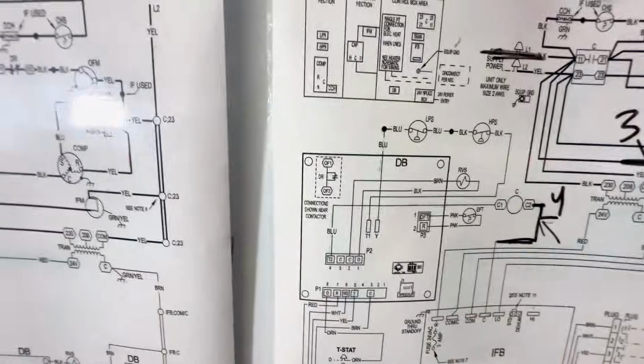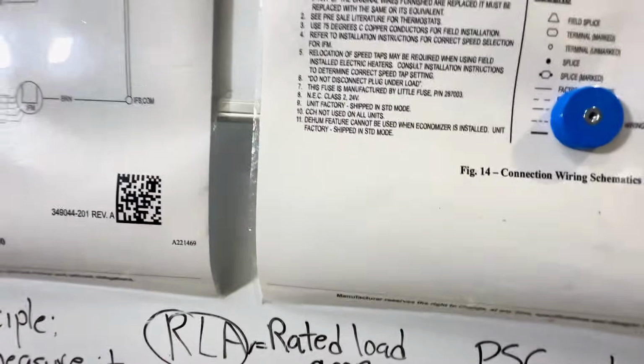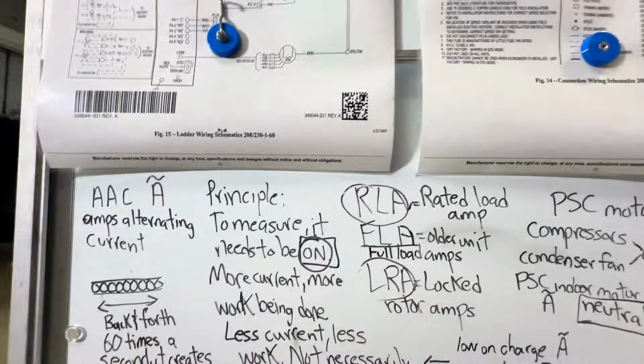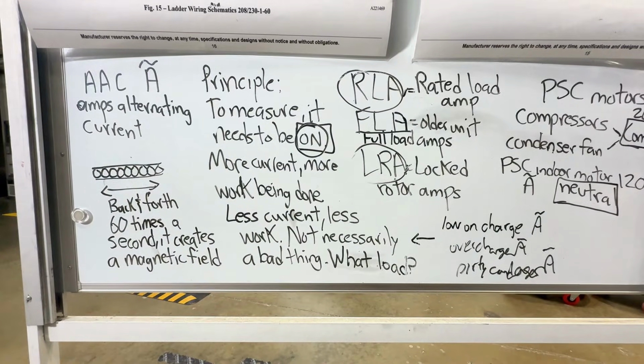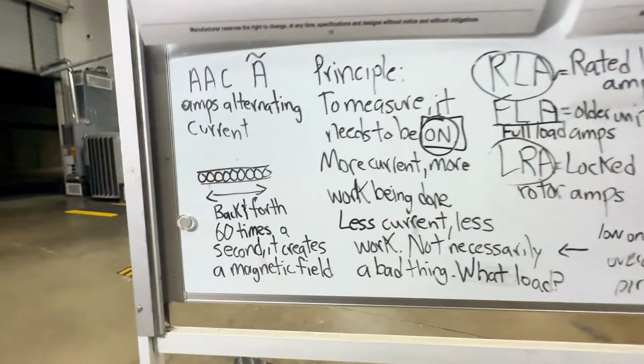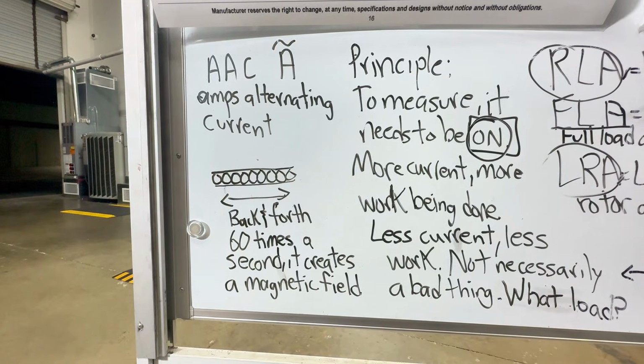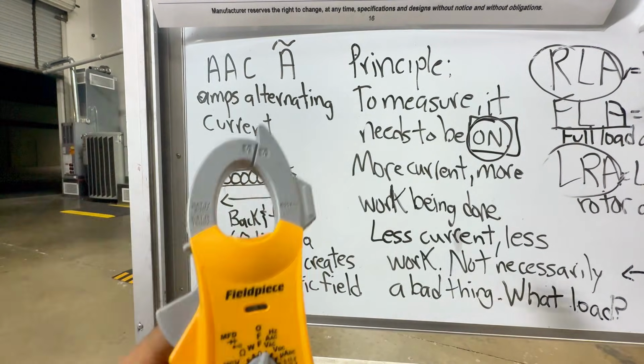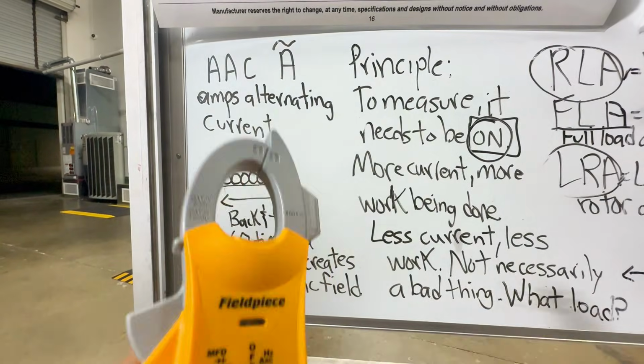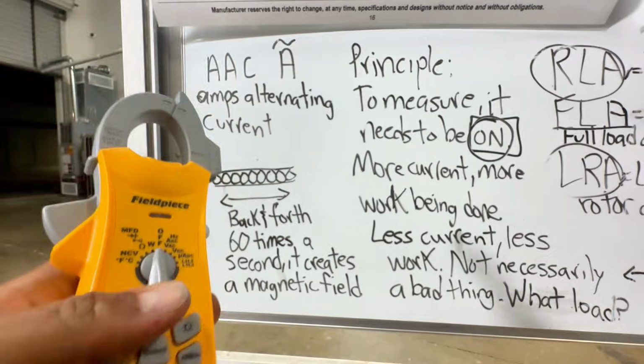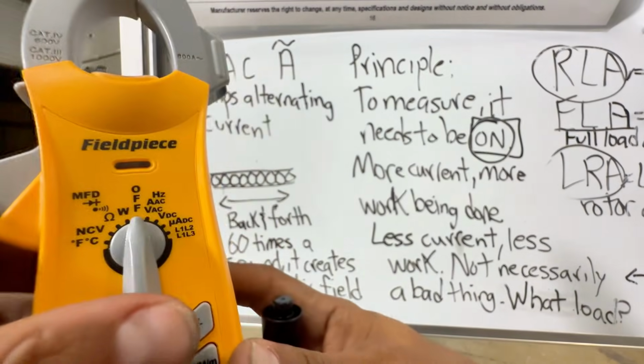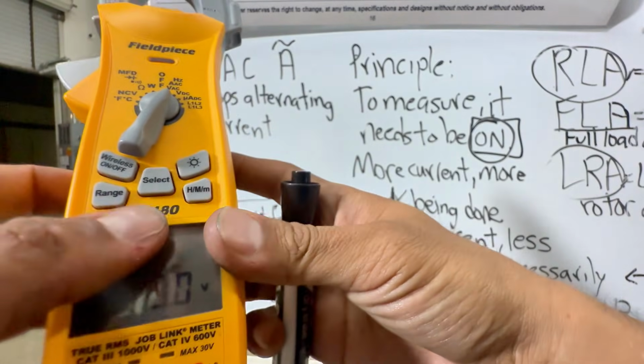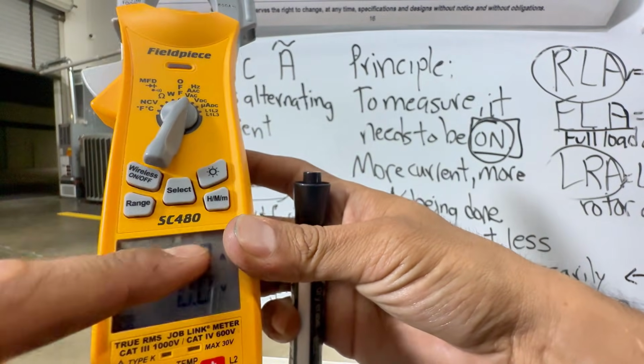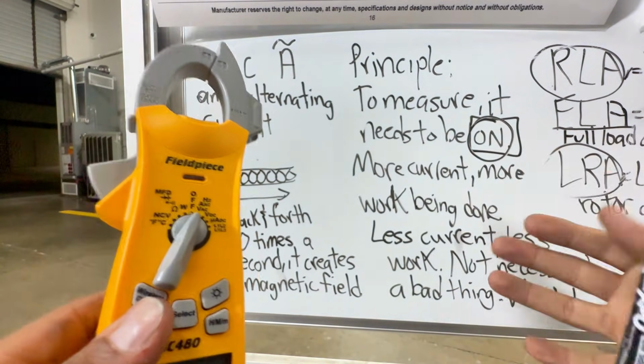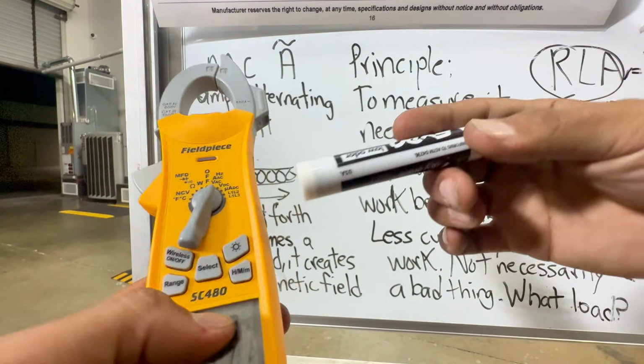But let's go ahead and get a clear explanation, because before we move forward, we need to understand a couple of things. Okay, so right here, amps, alternating current. So the way you check for amp draw is you have to have a meter that has, you see that? AAC, amps alternating current. And on this one, you actually have to go to that setting and press select, and then it shows up on top. Some meters are automatic, but this one you actually have to press select.